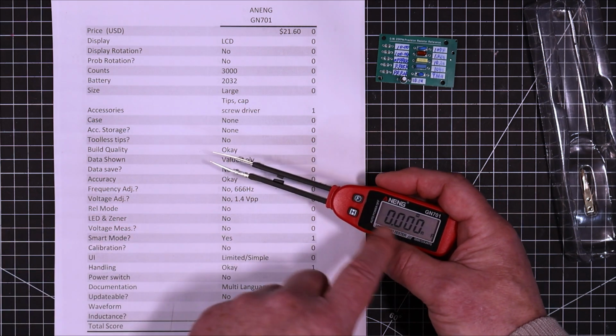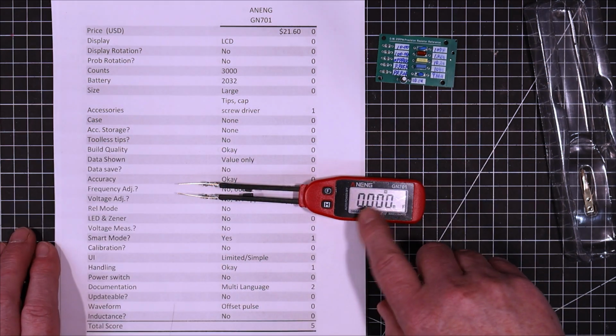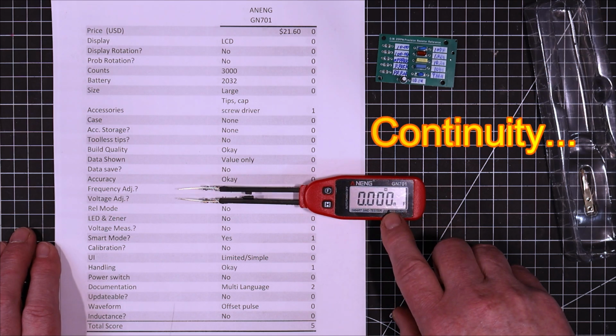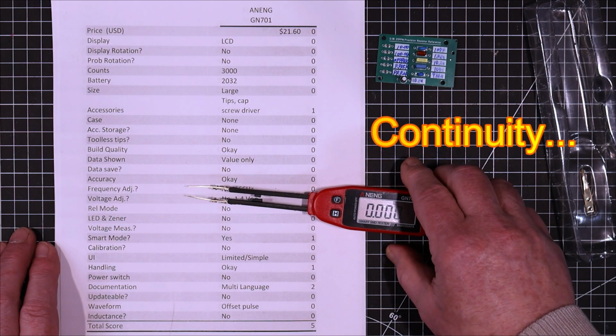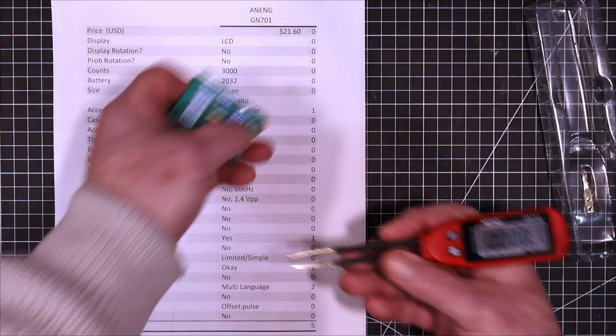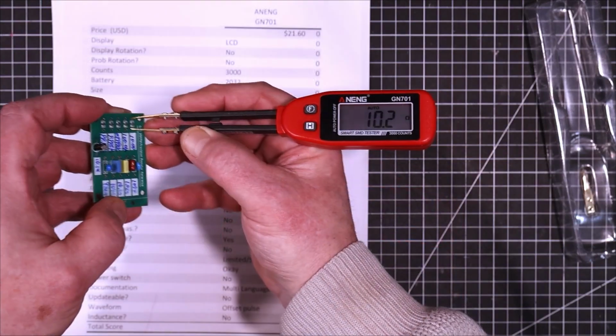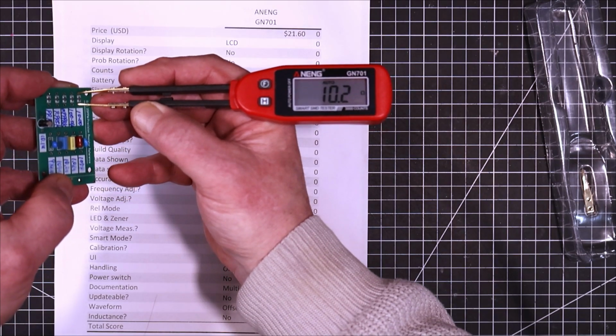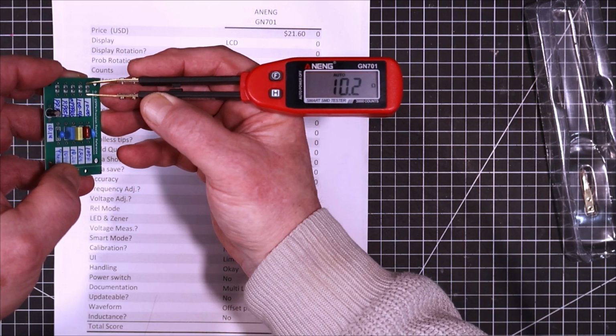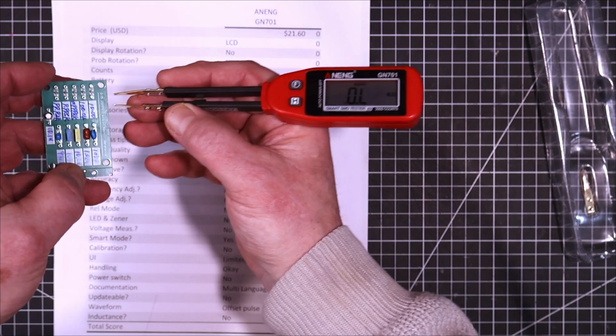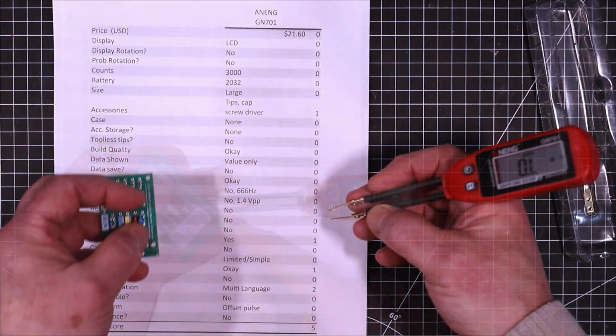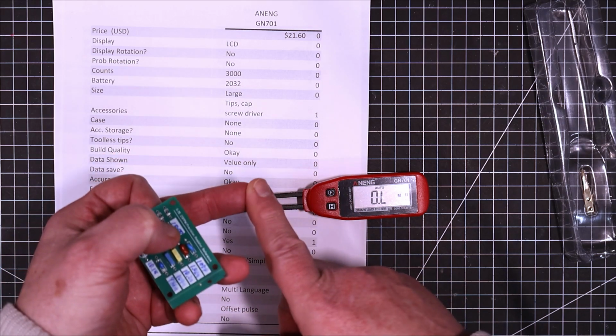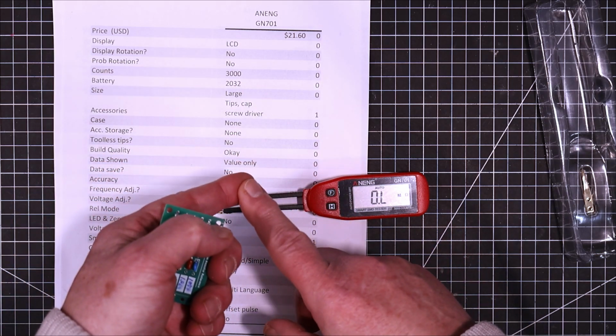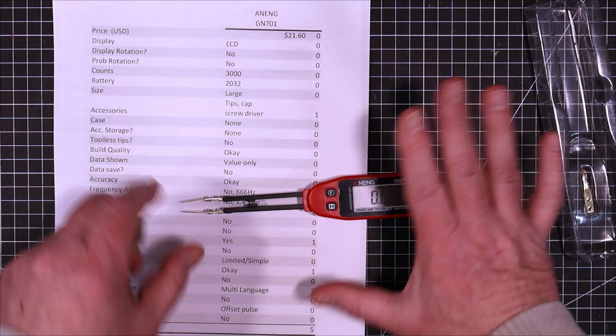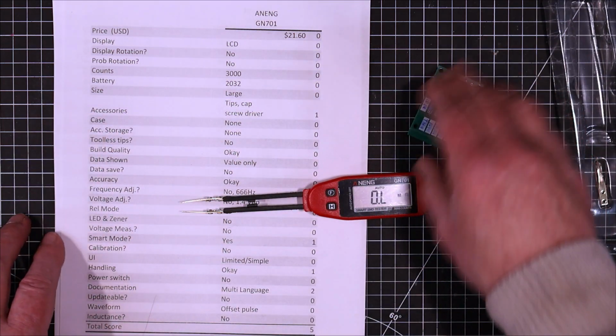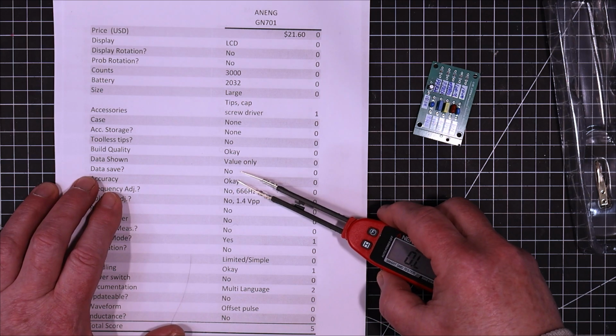The data shown, it gives you the value only. It can measure resistance, capacitance, continuity, and diodes, and all it'll give you is just the value. So if you look here, if we go and get this resistor here, this here is a 10 ohm resistor. It reads it within specifications. It doesn't give you any other information, so it just gives you the value. So if this was a capacitor, it would give you the capacitance, but it will not give you ESR, you will not get the Q factor, you will not get the loss angle, you will not get the impedance, and you will not get the reactance. Just the value only. And actually most of these meters are like that. Okay, so value only. Data save? No, you cannot save the data.